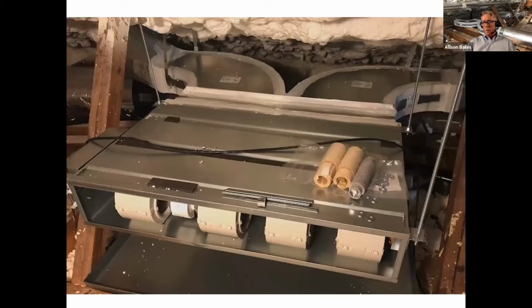But in passive house and high performance homes, there are these things called variable capacity mini split heat pumps. And yes, you can get them with higher static pressure, and we do a fair number of our designs with the higher static versions of these, because we don't always have control over what the contractors and the installers are going to do with the duct system. So we often will go with the higher static units, but the low static units are great. They use less energy. You just have to make sure the ducts are going to work with them.